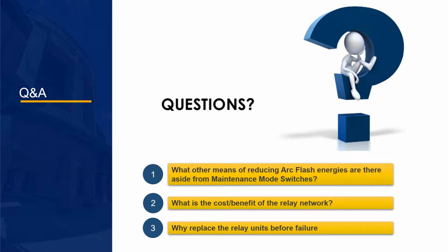What is the cost benefit of a relay network? As the relays come pre-configured to connect to a network, the only setting addition to the relay is entering a predefined IP address. The only other additional costs are potentially a network switch if your installation does not currently have one, or spare ports to support all relays, and the installation costs of running fiber or Cat Ethernet cable to all relays. The benefit is that there is no need to check the metering data, event reports, settings, or perform relay operations from directly in front of the switchgear where the relays are located. All of this can be performed from the safety of the control room or your office.